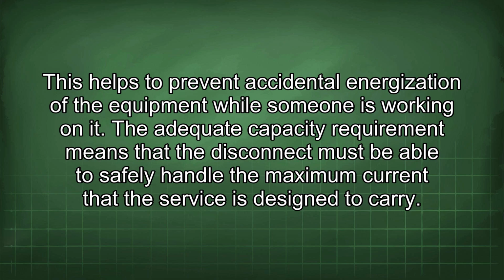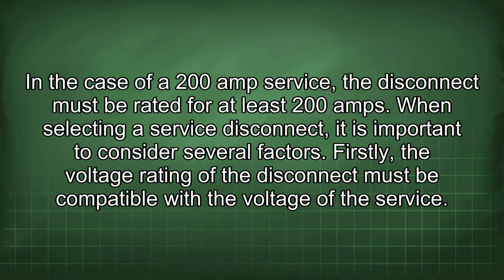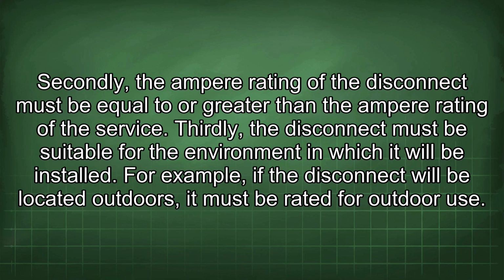The adequate capacity requirement means that the disconnect must be able to safely handle the maximum current that the service is designed to carry. In the case of a 200 amp service, the disconnect must be rated for at least 200 amps. When selecting a service disconnect, it is important to consider several factors. Firstly, the voltage rating of the disconnect must be compatible with the voltage of the service. Secondly, the ampere rating of the disconnect must be equal to or greater than the ampere rating of the service. Thirdly, the disconnect must be suitable for the environment in which it will be installed. For example, if the disconnect will be located outdoors, it must be rated for outdoor use.